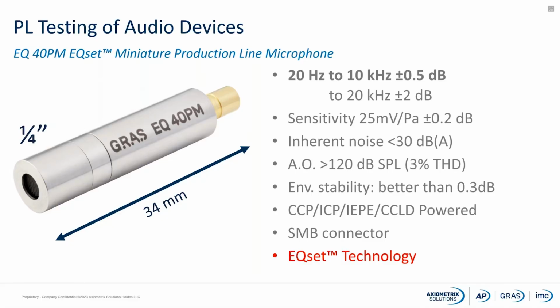We're going to talk further about environmental stability in another slide, but we can say that it's better than 0.3 dB. The microphone is powered using a CCP power supply, which is one of the most common microphone supplies used with test and measurement equipment. ICP, IEP, CCLD are other names for compatible technologies. So if you have a data acquisition system or analyzer that has IEP or ICP or CCLD microphone power supply, it means that it's going to be compatible with our EQ40PM microphone.